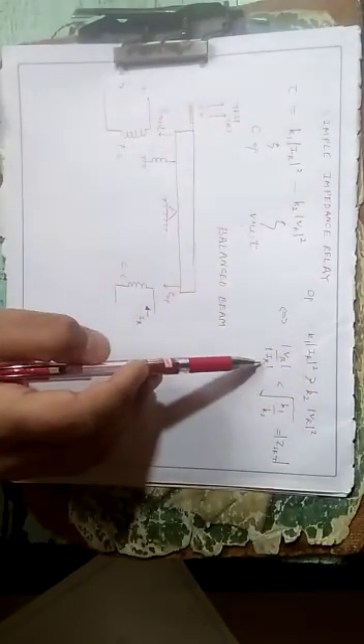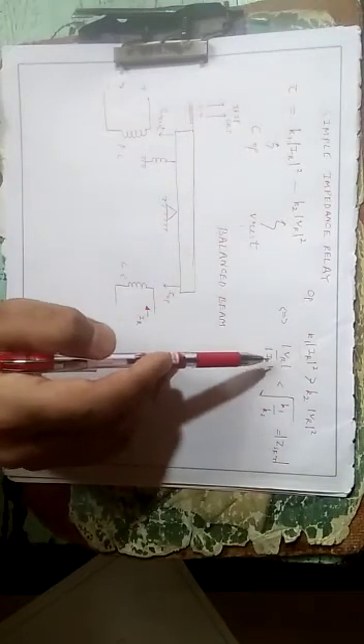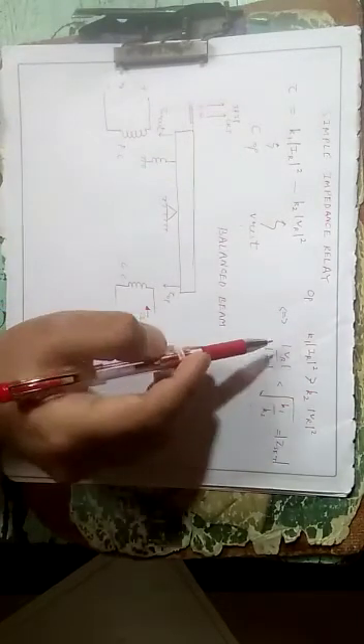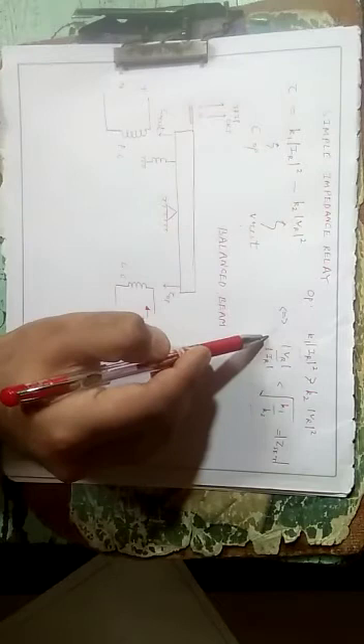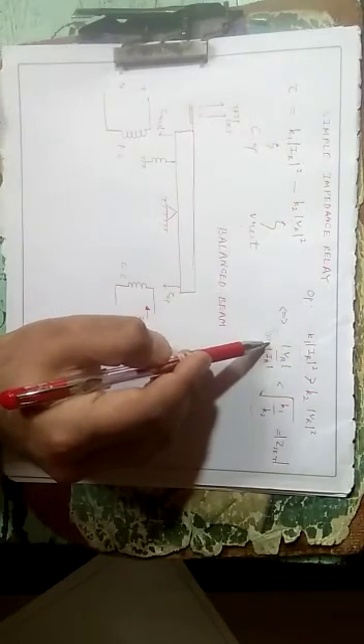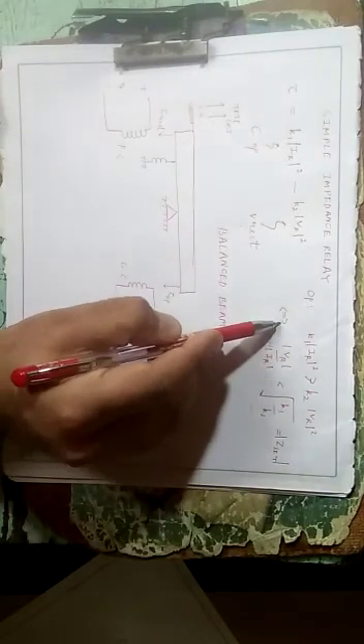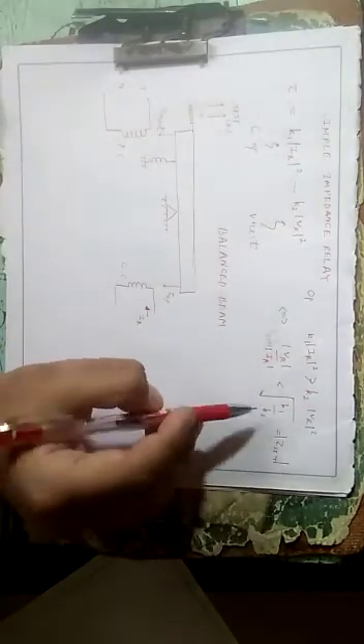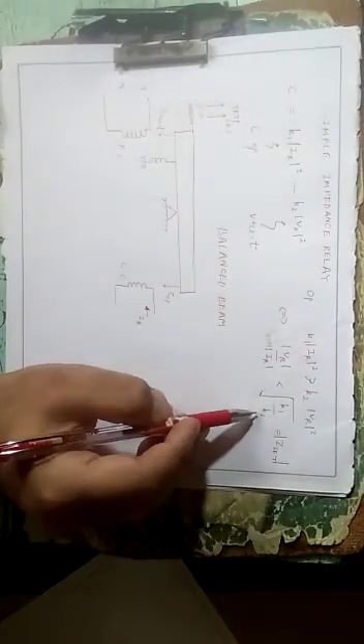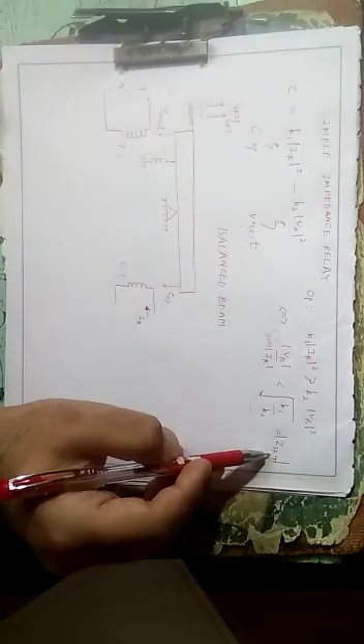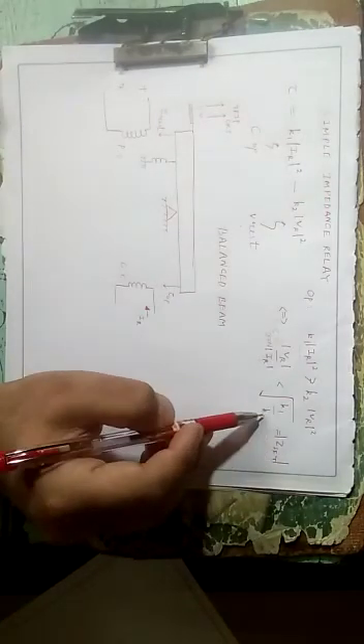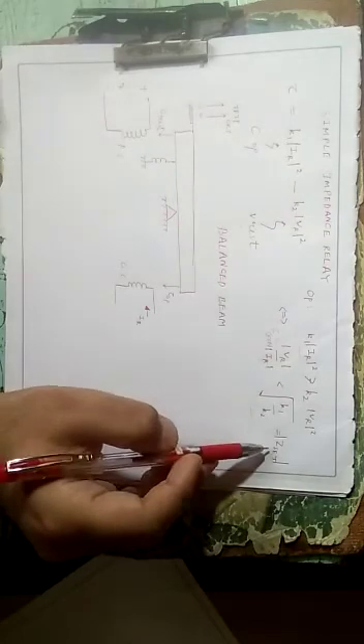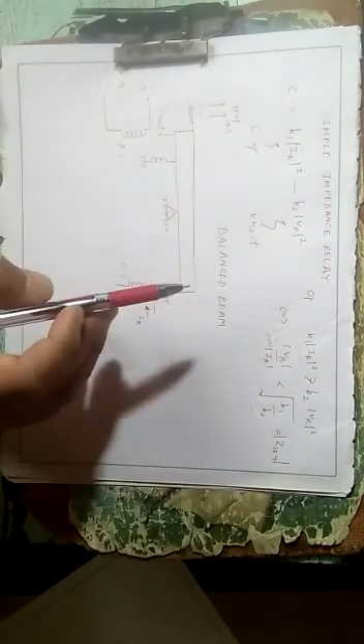After some algebraic manipulation, we can see the ratio of voltage and the current, which is nothing but the impedance as seen by the relay. This is less than square root of k1 by k2, which is nothing but the set point of the relay, the setting impedance. By manipulating k1, k2 or both, we can change the reach of the relay. This is a simple way.